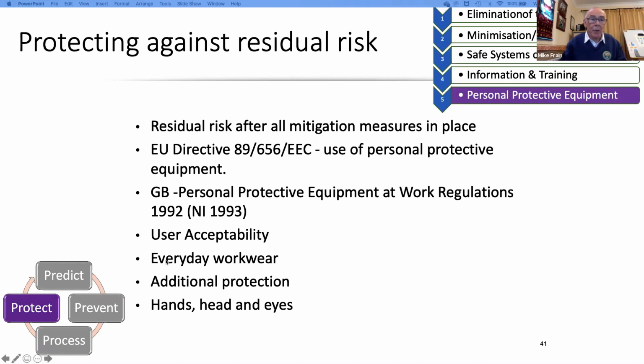So everyday workwear is something I would suggest, if you've got an arc flash incident energy level on particular equipment, even at low level, perhaps consider that, particularly because non-arc flash clothing can ignite. So I would always push people, if they have got those risks within their workplace, to consider everyday workwear. Consider additional protection on top of that, and hands, head and eyes, don't forget that hands are going to be much closer to the source of the arc.